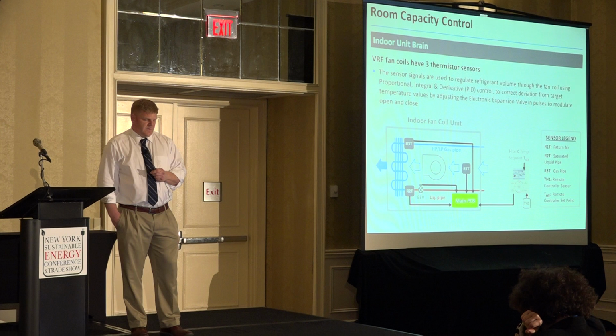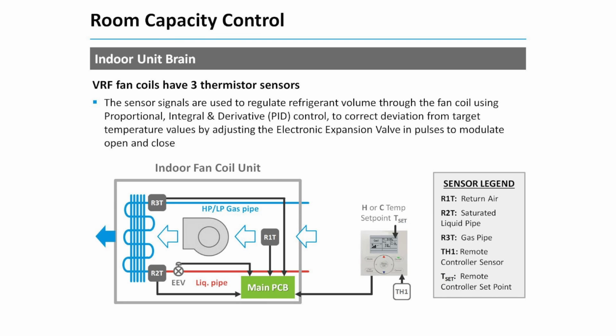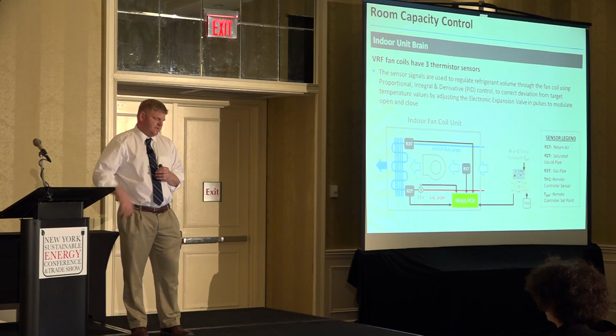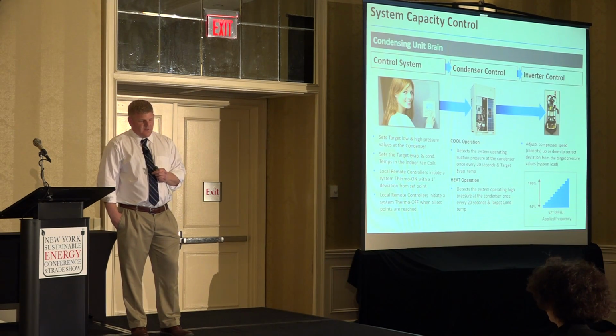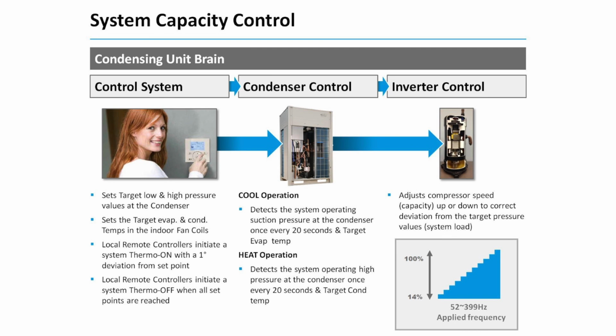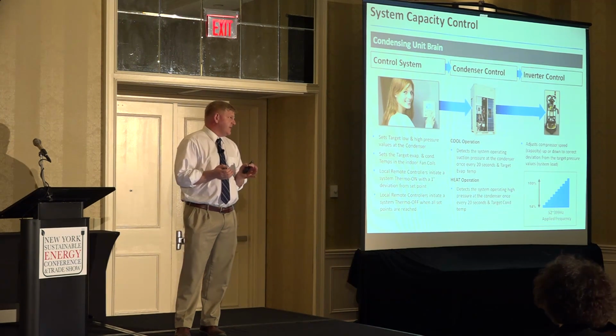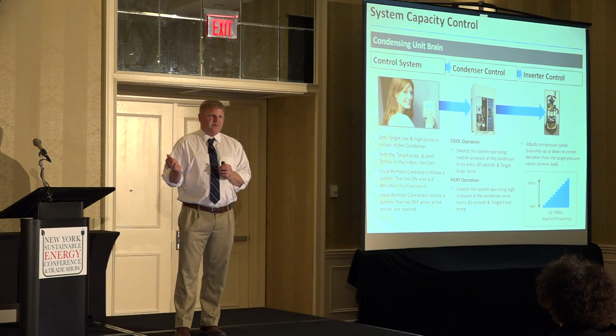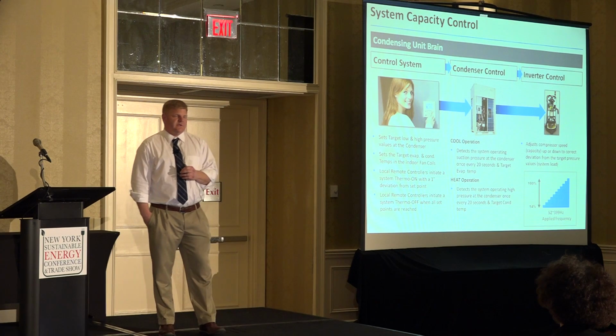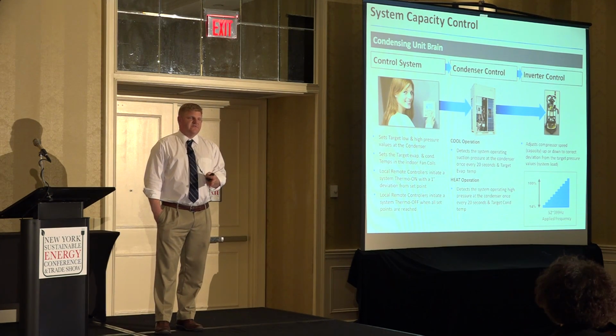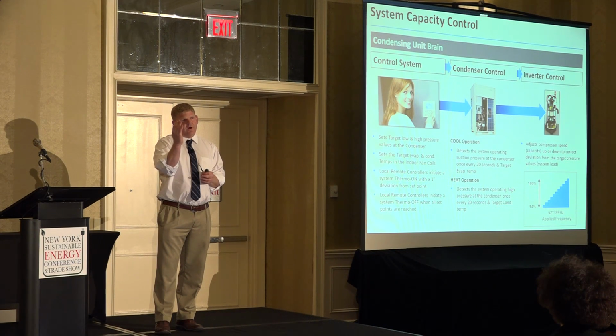Each indoor unit has thermistors on it, and we're constantly measuring and sending feedback to that outdoor unit about where we are in terms of set point and how hard we have to work to maintain a comfortable and tight variance. So that outdoor unit has an inverter compressor in it that will slow down, and that's where you get your electrical savings. The majority of the time, these buildings that we occupy very rarely are at peak demand. They're more often than not within a 40 to 70% profile as far as what actual capacity they may need. So that's where we get the energy efficiency out of these systems, is that they'll slow down and they won't work as hard when you don't need it.